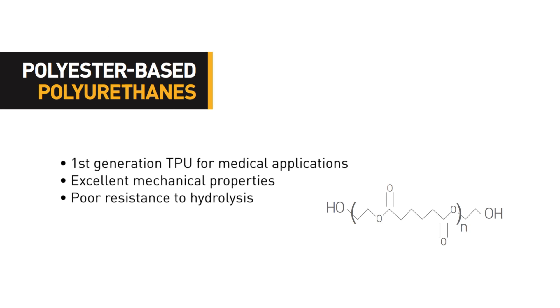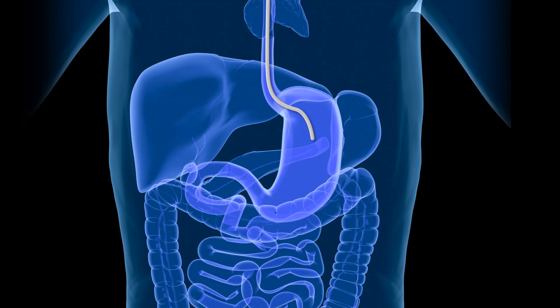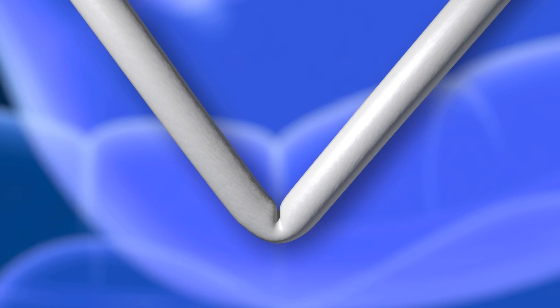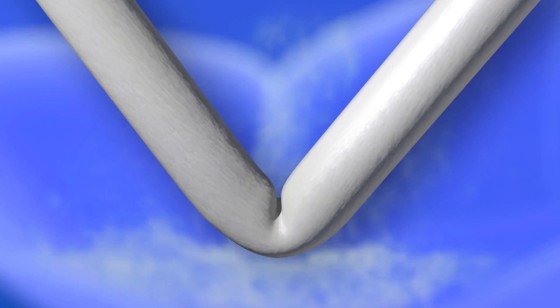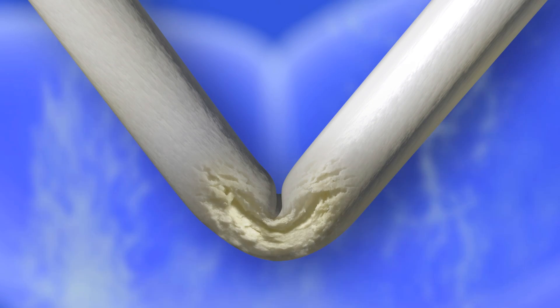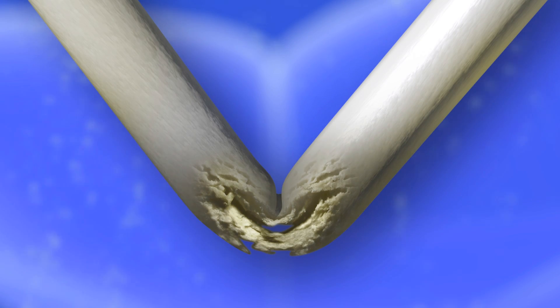Polyester-based urethanes were some of the first polyurethanes used in medical devices. These urethanes have the best mechanical properties, but were quickly found to rapidly degrade when introduced to the body. This rapid degradation is due to the susceptibility of ester groups to water-based hydrolytic cleavage, causing weakness and loss of integrity.